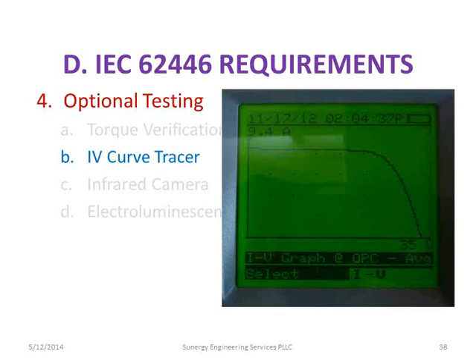So is everybody familiar with the IV curve trace? This axis is the current. This axis is the voltage. And basically an IV curve tracer makes the module go through all of its different iterations under different conditions of how it would be operating. So this is the same thing that the manufacturer does when they get a curve traced to tell you what's on that sticker and what the specification on the module is on the back. That's the same way they do it.